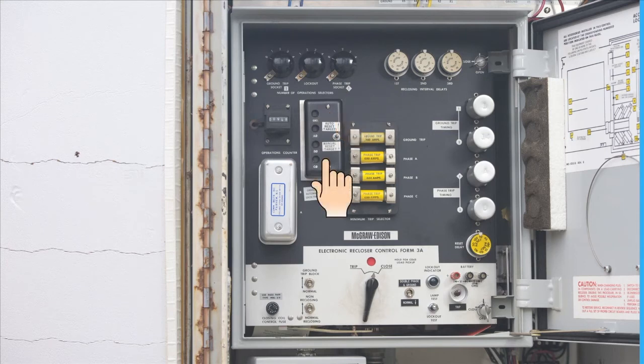When current above the selected minimum trip level is detected in 1 or more phases, the following chain of events will occur for an operating sequence of 2 fast and 2 delayed operations. The overcurrent signal is integrated with time on the characteristic curve of the timing plug to produce the signal which energizes the trip circuit. Energizing the trip circuit connects the battery to the trip solenoid, tripping the recloser. Simultaneously, the sequence relay advances to energize the first reclosing interval delay plug. Upon expiration of this reclosing interval delay, a closing signal from the control closes the recloser, and the sequence relay sets up the circuitry for the second fast trip operation.